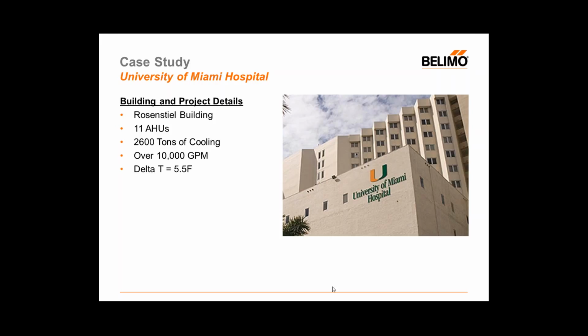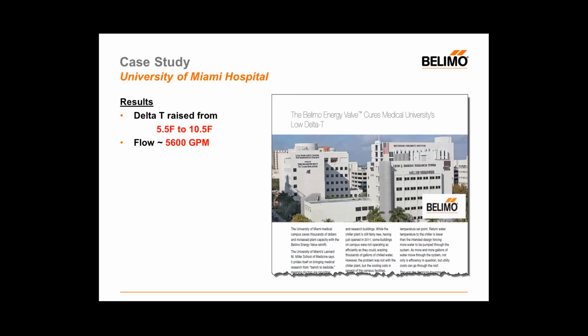And when they got there, they were pumping over 10,000 gallons a minute through the building at about a 5.5 degree delta T. Each of the air handlers was retrofit, all 11 of them, and we were able to get delta T to be raised from 5.5 to 10.5 degrees Fahrenheit and cut the flows from around 10,000 to right about 5,600. So substantial reduction in the amount of water used to cool the same space, the same amount.